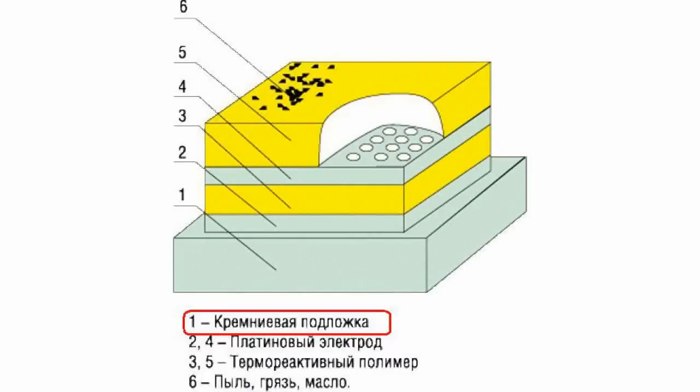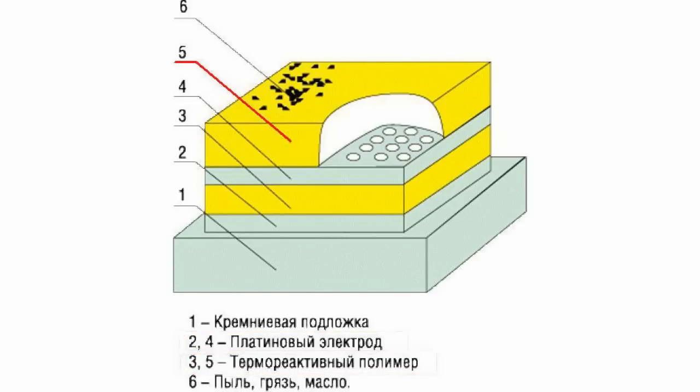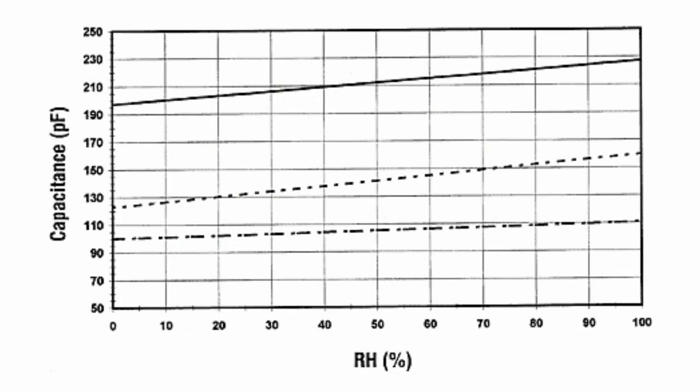Capacitive relative humidity sensors are widely used industrially in a variety of commercial applications and weather bureau. They consist of a substrate on which a polymer or a thin layer of metal oxide is coated between two metal electrodes. The sensitive surface is covered with a porous metal electrode to protect it from contamination. The substrate is usually glass, ceramic, or silicon.